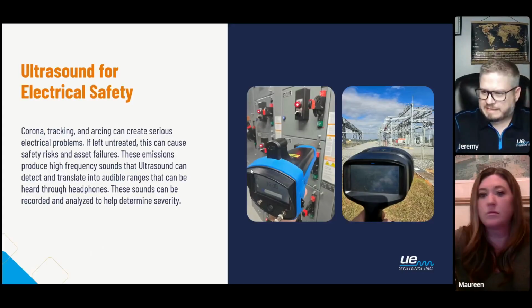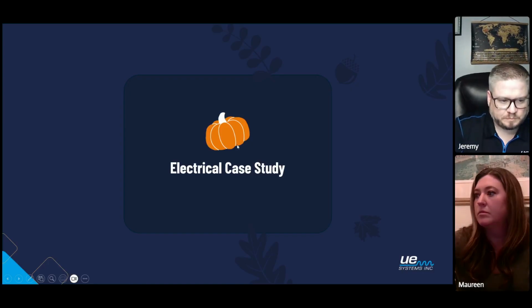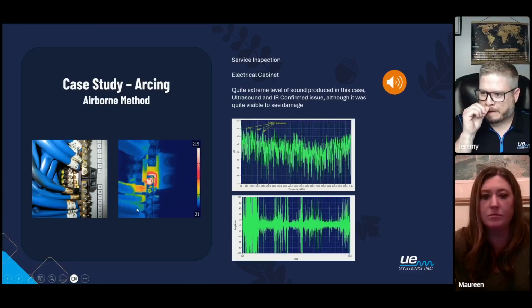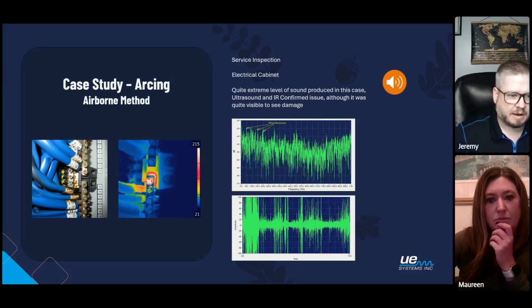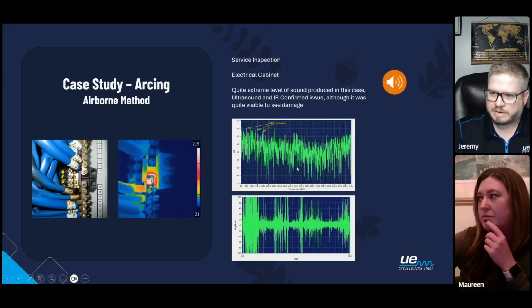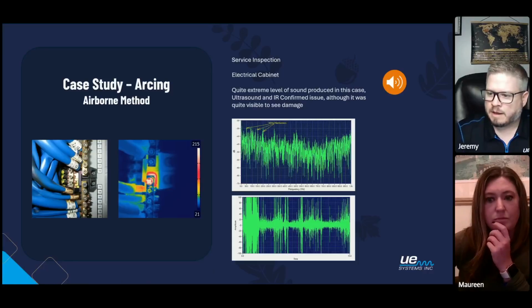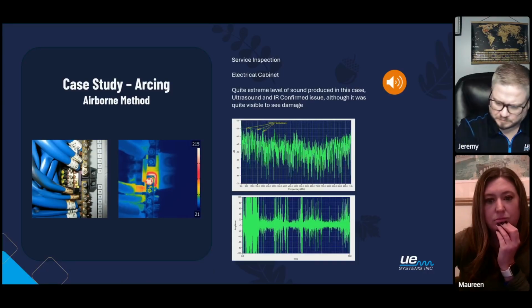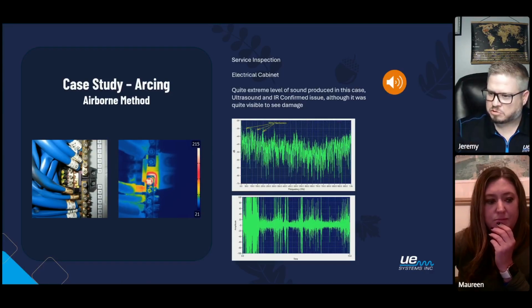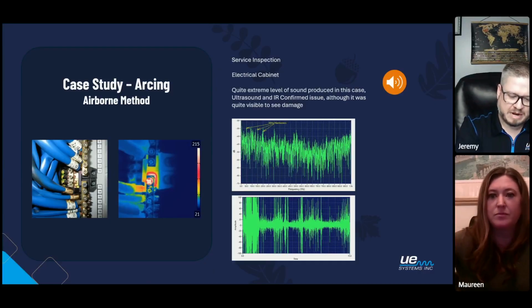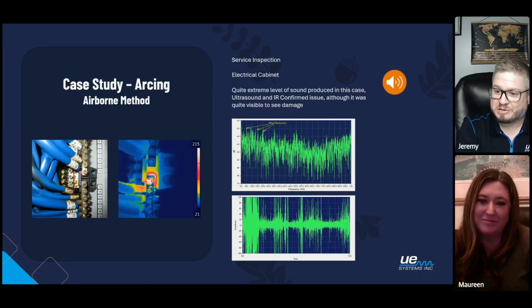So the case study I'm going to share here. This was a team that was going out and doing their normal inspections and their cabinet scans. They do an external scan with an airborne using Ultraprobe 10,000. They're scanning and listening for any kind of electrical discharge or any sounds that seem abnormal to them. Typically, you'll go out and scan the whole area. The rule of thumb is no noise is good news.